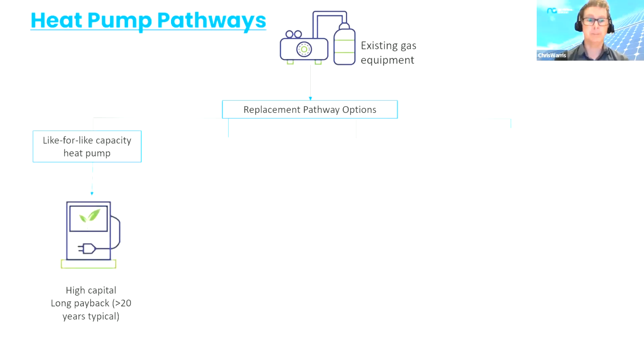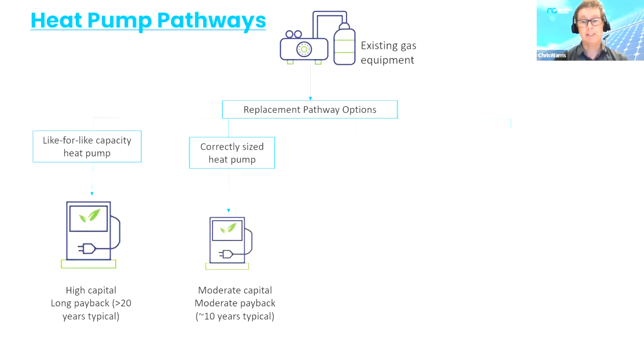You can do the like for like capacity heat pump. It's going to have high capital and a long payback. What we often find though is that because gas boilers are relatively cheap, they're often oversized. They're just over-designed to have 50% extra or 100% extra capacity just in case. And you can do that when you've got a cheap boiler. You just can't afford to do that with heat pumps because the capital cost is higher.